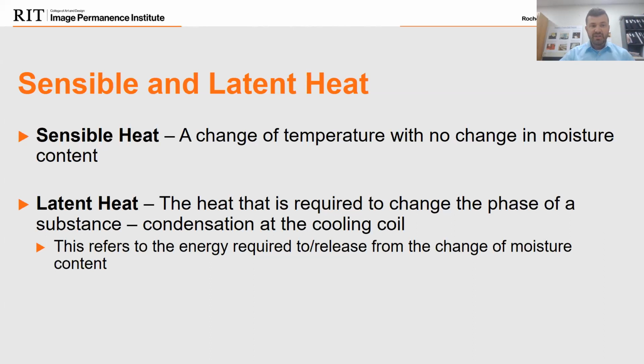So it's two different terms. When you're talking to any facilities or a mechanical person, and they talk about sensible heat or latent heat, those are the two different terms. Again, sensible is that change in temperature, no change in moisture, and latent is a change of phase to a substance.